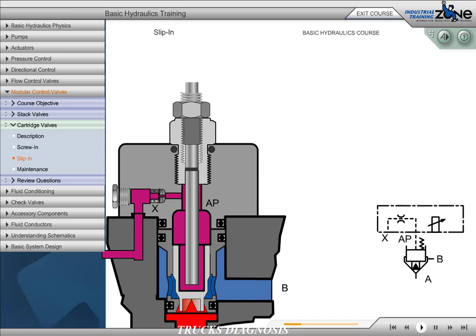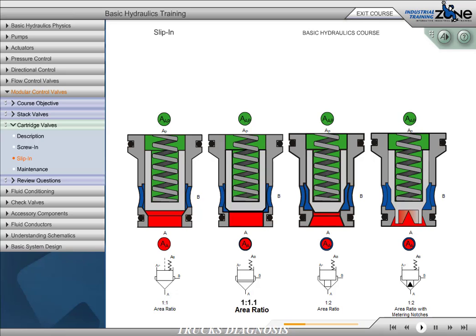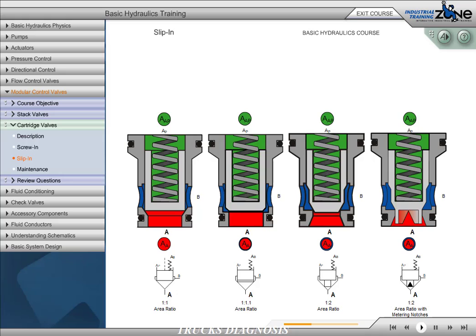Slip-in cartridges are typically used in circuits with flows of 30 gallons per minute or more. The poppet element of the slip-in cartridge is available in several area ratios: 1 to 1, 1 to 1.1, 1 to 2, and 1 to 2 with metering notches. Notice how the symbols are drawn to show the difference in area ratios. The ports are typically labeled A, B, and AP. A and B are the work ports, and AP is the pilot port. The pressure at each port, area ratios, and spring force will determine whether the valve will be open or closed.